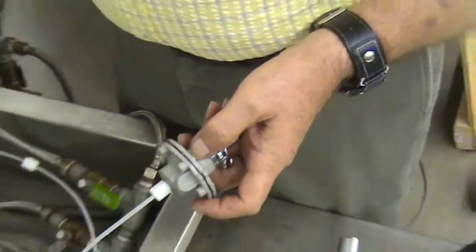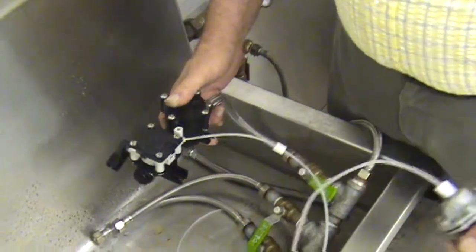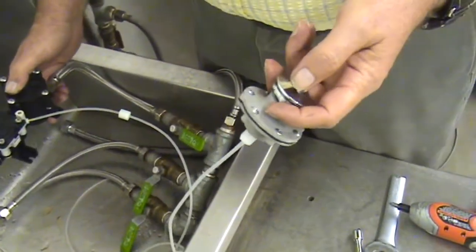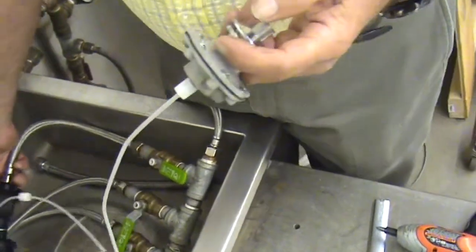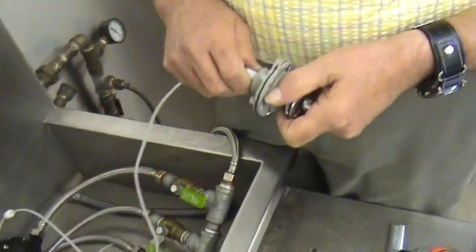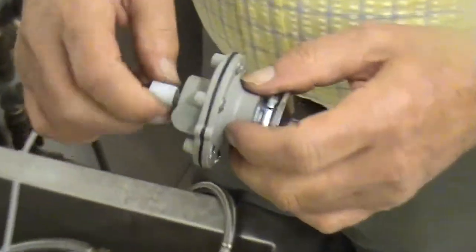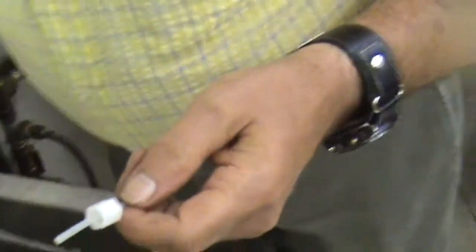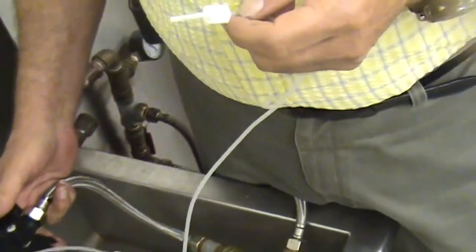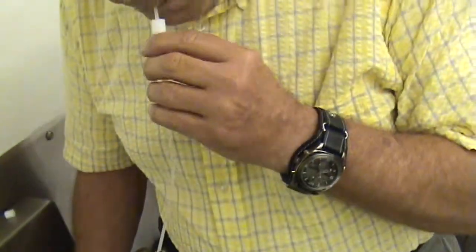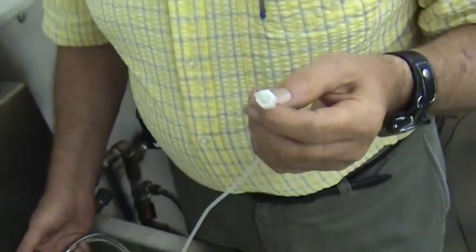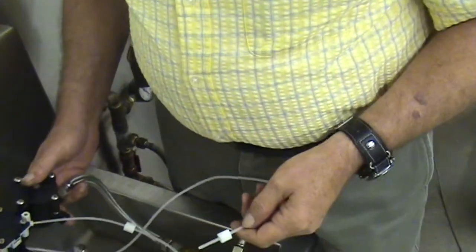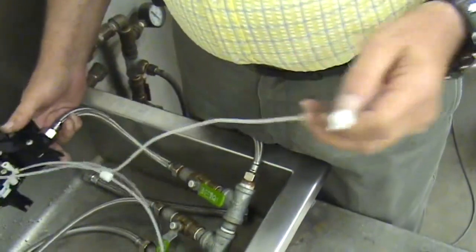We checked the check stop already. We fixed a drip at the end plug. And we tried a new operator on it. And without any good results from the new operator, we're going to disconnect the tubing from the push button assembly. Slide that tubing back and use our house to create the vacuum to see if that will operate the valve. If we're successful in operating the valve like that, we know the valve is working properly. And we don't need to look any further in that valve.